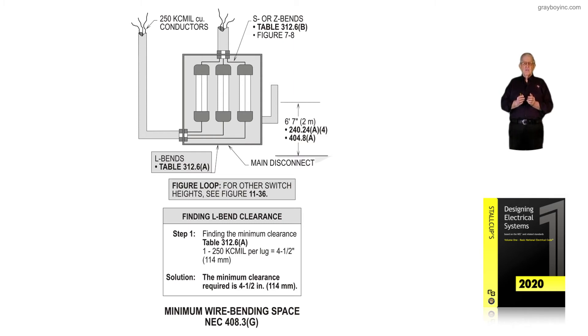Notice that to the center of that handle in the on position, the maximum height is 6'7", but there is no minimum height listed. Per NEC 240.24A4, those fuses have to be readily accessible.